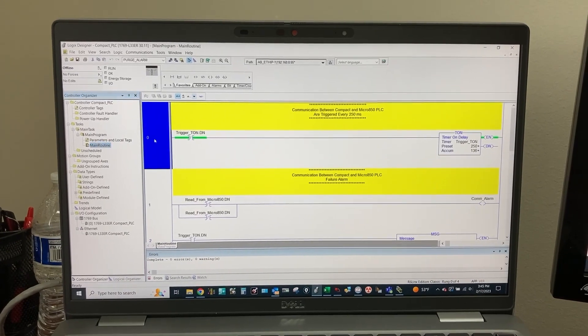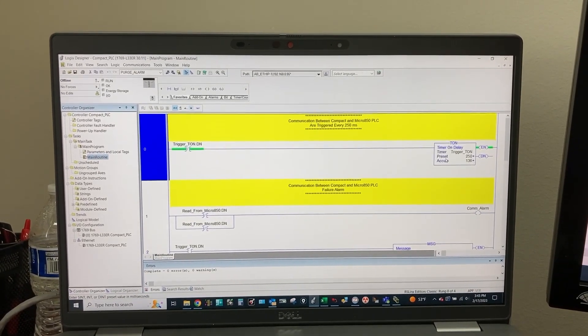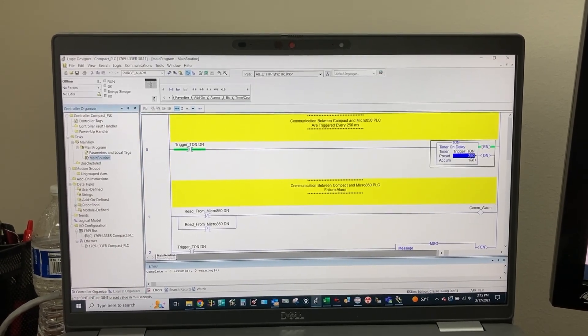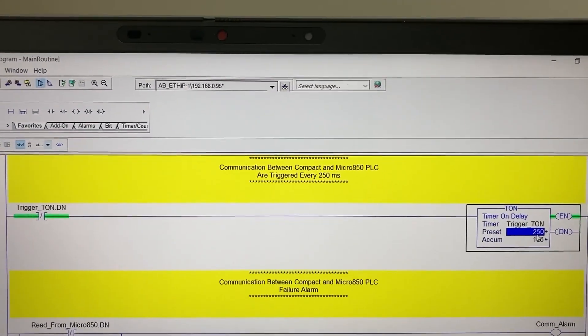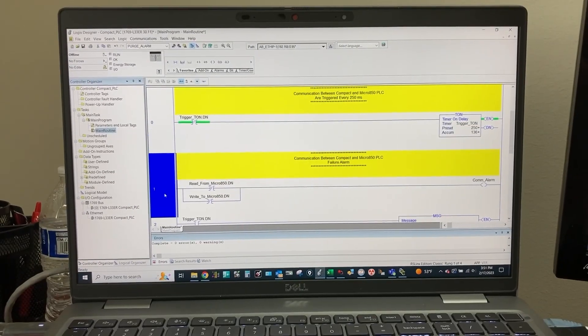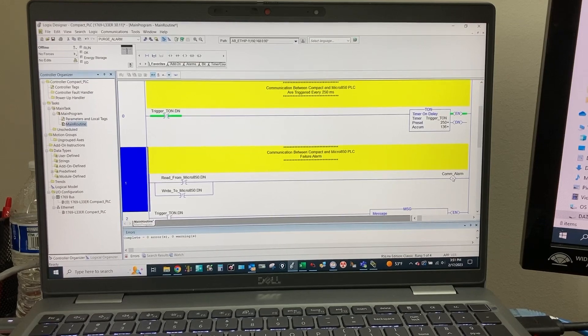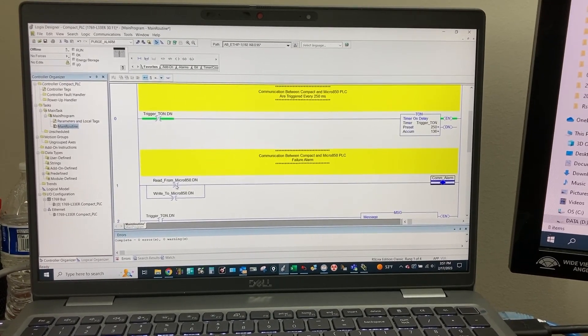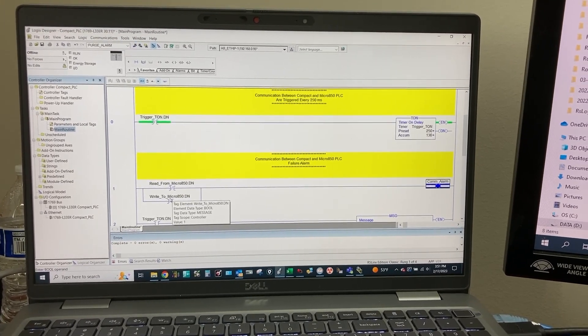The first rung, Rung 0, is for the timer for the communication to get triggered every 250 milliseconds. The second rung, Rung 1, is for the communication failure alarm that is triggered from either the read or write message instruction block.